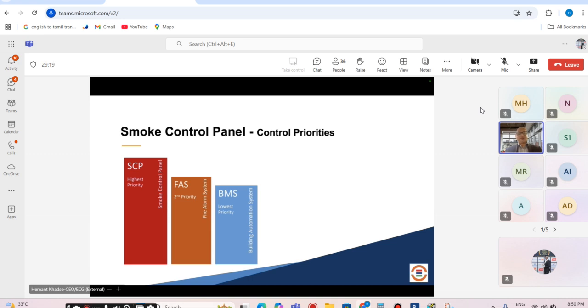IBC or NFPA, or even for that matter your local codes in UAE and India, are also very, very focused in terms of smoke management, and it becomes a priority system. When you look at a clear clause in IBC, it is very clearly spelled out that smoke control must be given the highest priority, followed by fire alarm, and then BMS.